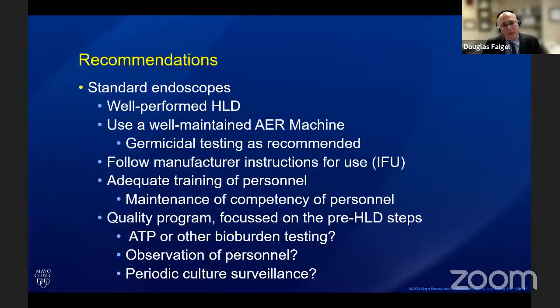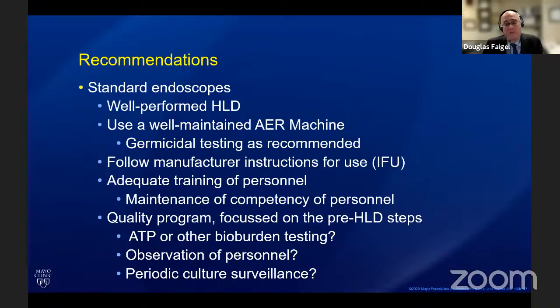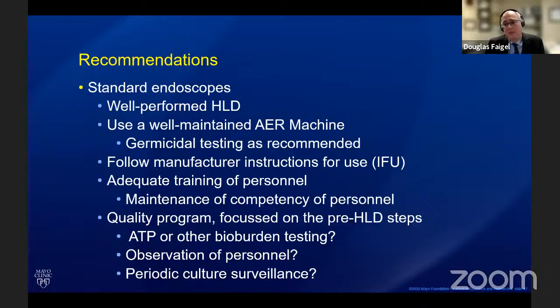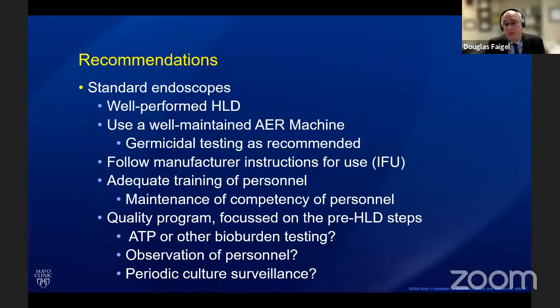For standard endoscopes, perform well-done HLD using a well-maintained automatic endoscope reprocessor, test the germicide as recommended, follow the manufacturer's IFU instructions, ensure adequate training of personnel and programs to maintain competency, and have a quality program focused on pre-HLD steps especially manual cleaning — potentially including ATP or other bio-burden testing. Periodically observe personnel and consider periodically culturing duodenoscopes to survey for contamination. A well-performed pre-cleaning is a must for both HLD and sterilization to be successful.